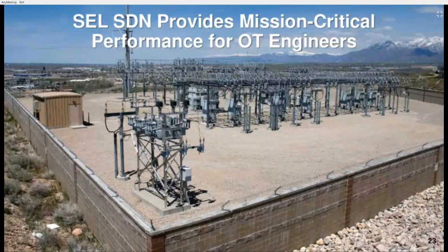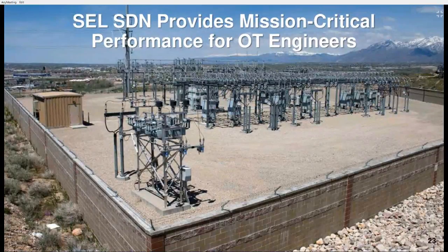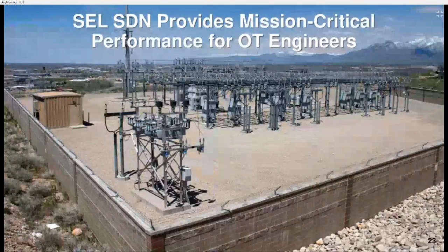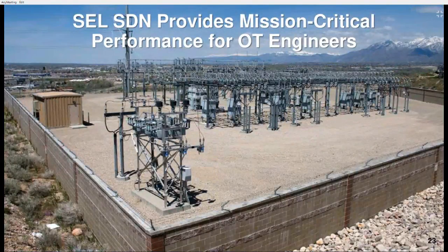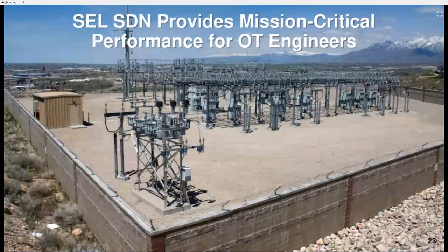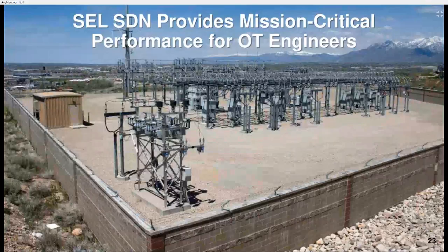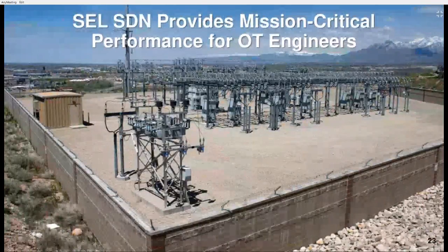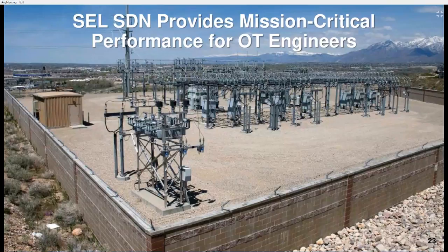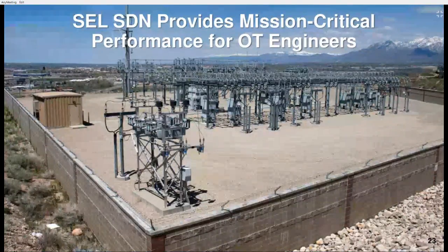SEL knows that protection events typically occur at the same time that communication events happen. When communication that is already not as fast as the power signals has an outage, when we need the protection traffic the most, there's a problem. As an IT network and systems engineer, I heard the developers talking about fast failover times of 100 microseconds. I really could not press the I believe button until I actually got my hands on the device and tried it. The advertised time is 100 microseconds, but what we were seeing was less than 10 microseconds.